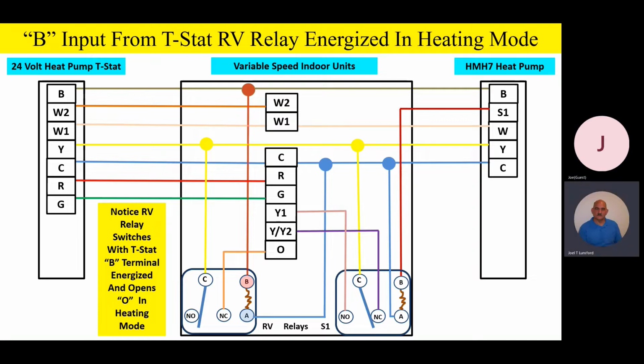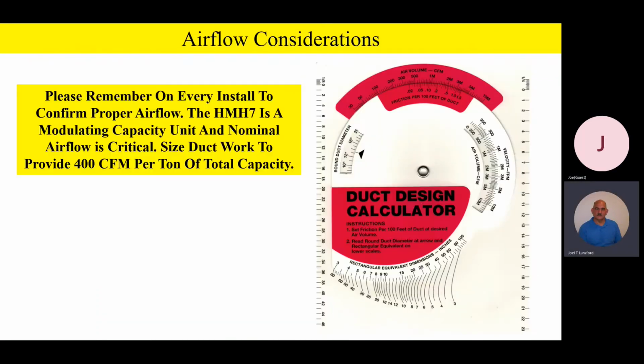All right. Well, fellas, let's talk a little bit about some airflow considerations when the contractors are building their ductwork. Please remember on every install to confirm proper airflow. The HMH7 is a modulating capacity unit, and nominal airflow is critical. We want to make sure they size their ductwork to 400 CFM per ton of total capacity. This is important, because it's a modulating system: if it sees reduced airflow, or if it sees the coil inside starting to ice up or freeze up, it's going to back off on the capacity.